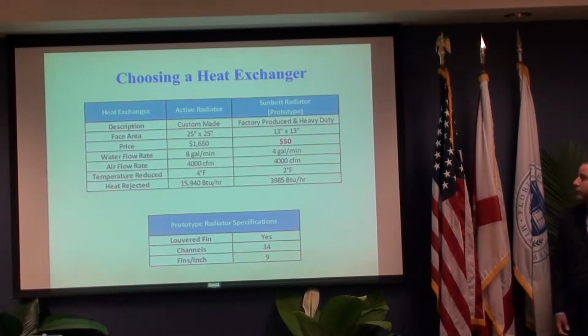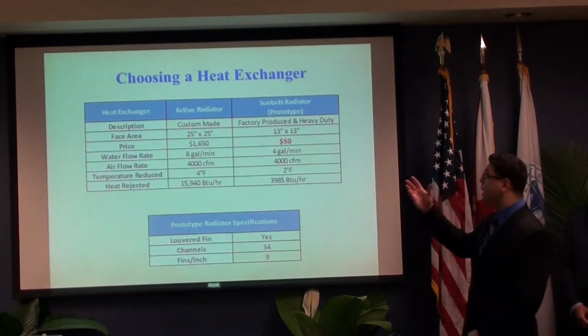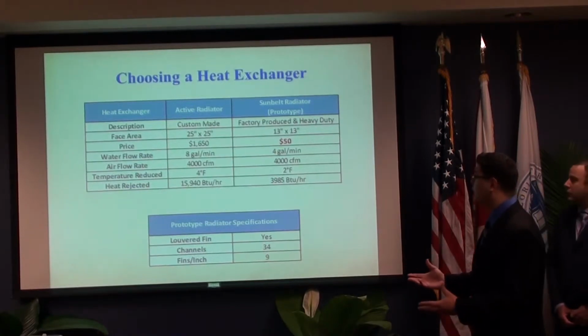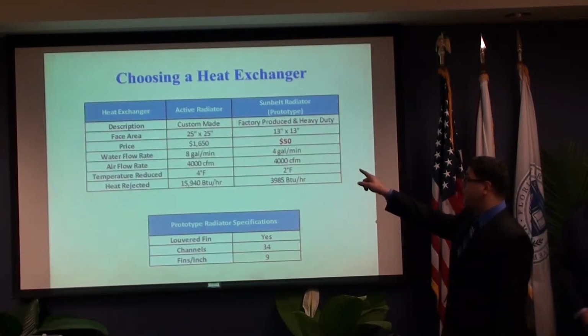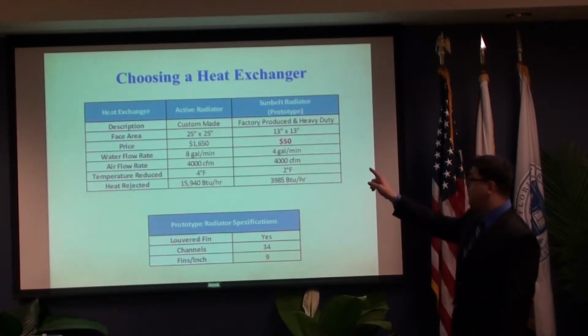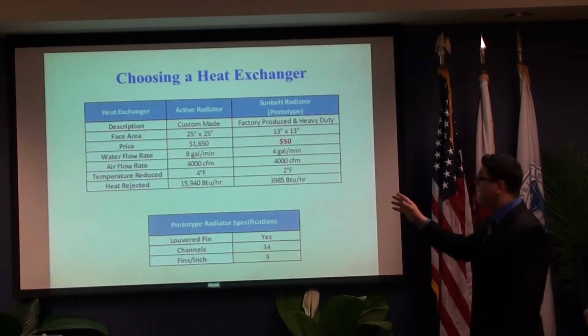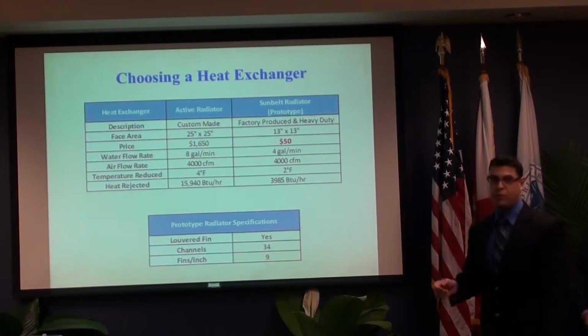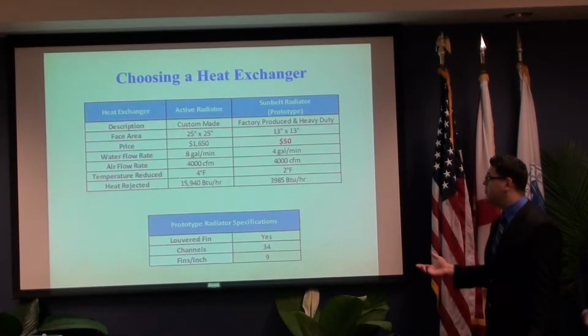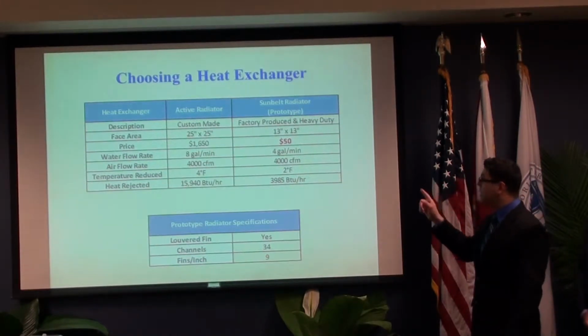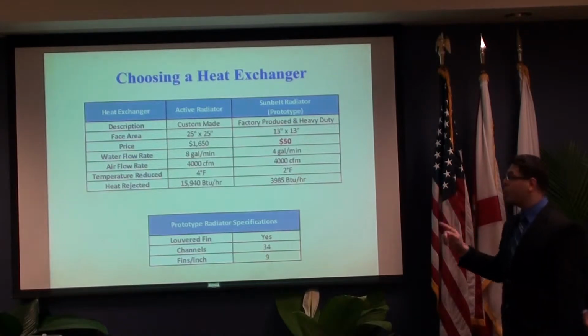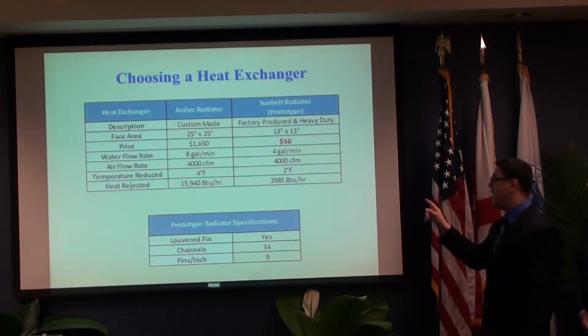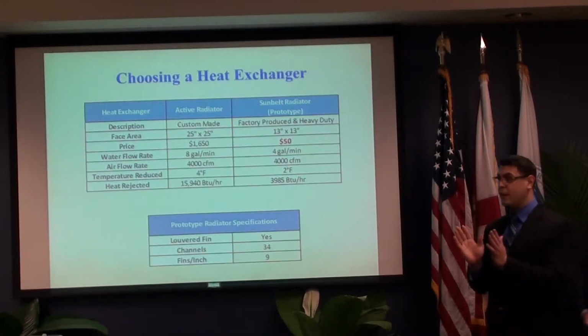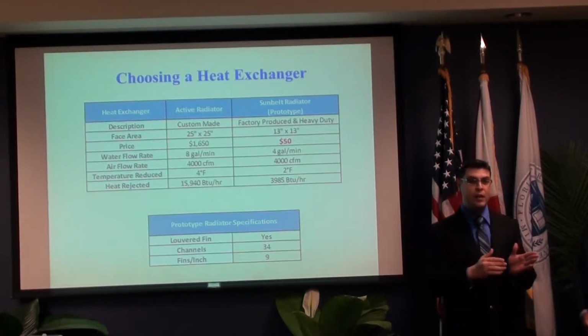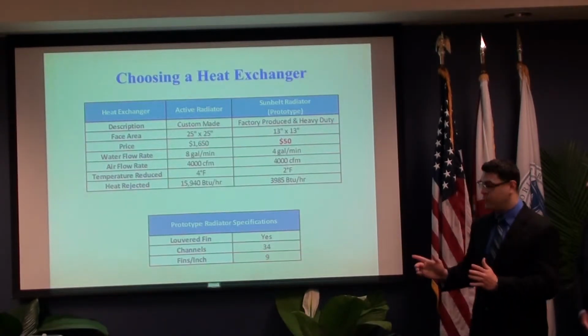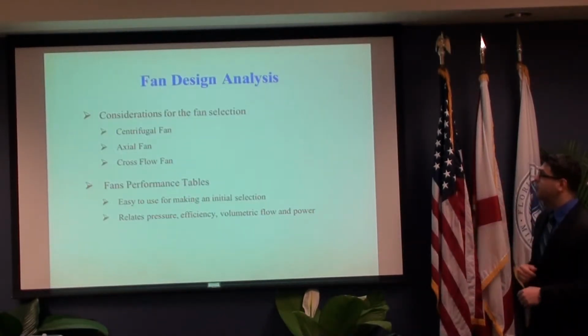Based on all these calculations, we found a radiator that would meet all of our specifications, including the 4-foot square, because we would have a face area of this radiator that was going to be 25 inches by 25 inches. However, the price was extremely high at $1,650. So we decided to come up with a prototype. We bought this radiator for $50 from Sunbelt Radiator, which is a local company, and it was going to reduce 2 degrees Fahrenheit. We were planning on buying 2 of these radiators so that we could put 4 gallons per minute in one radiator and 4 gallons per minute in the second radiator, and make it into a V shape inside the cooling tower.